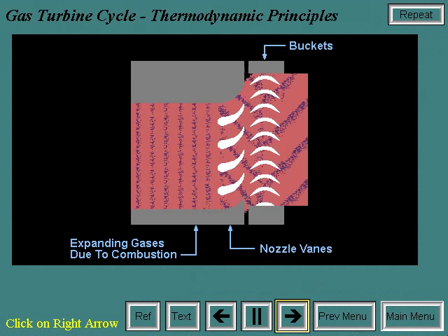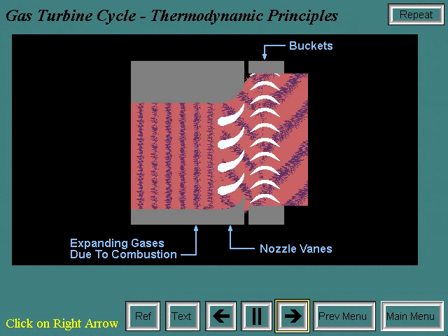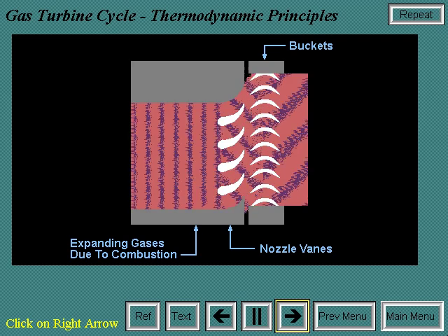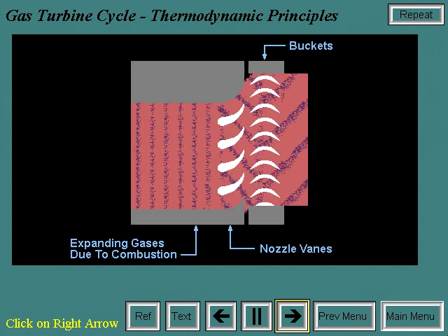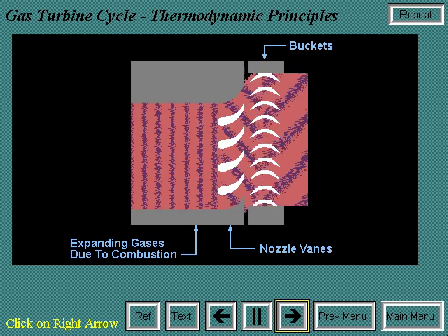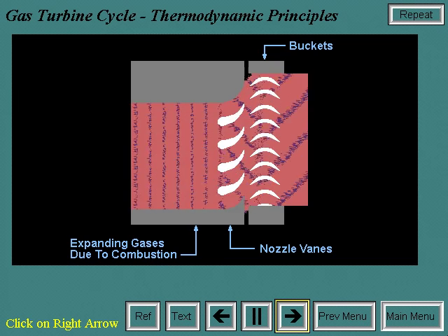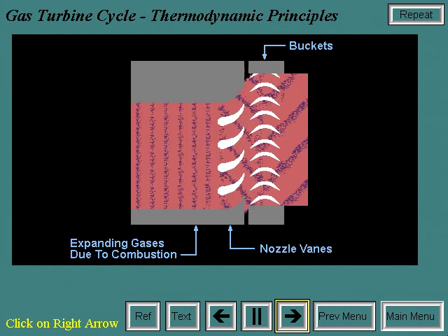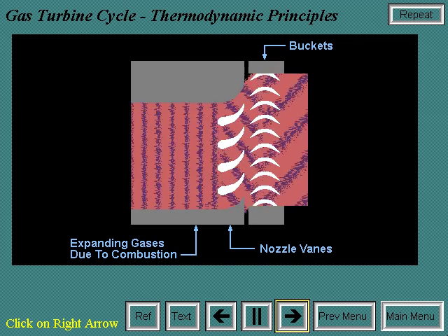The conversion of work in the turbine actually takes place in two steps. In the nozzle section of the turbine, the hot gases are expanded and a portion of the thermal energy is converted into kinetic energy. In the subsequent bucket section, a portion of the kinetic energy is transferred to the rotating buckets and converted to work. Typically, more than 50% of the work developed by the turbine section is used to power the axial flow compressor.